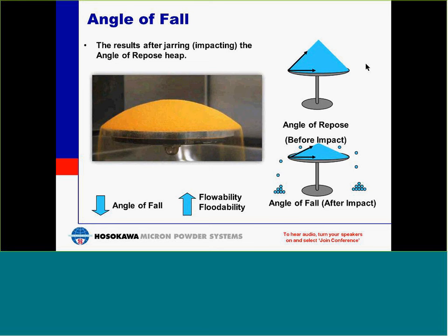One of the things I did not mention previously is that when you have a limitation on the small end, you also use a smaller diameter platform for doing the measurements. So there is really no limit on the lower end. On the upper end, quite frankly, the limit is that I feed it through my funnel, and my funnel can range up to 10 millimeters. This is a glass funnel, so we actually get a much, much larger opening, but the standard size openings are 8 and 10. There are two different sizes offered with the machine.